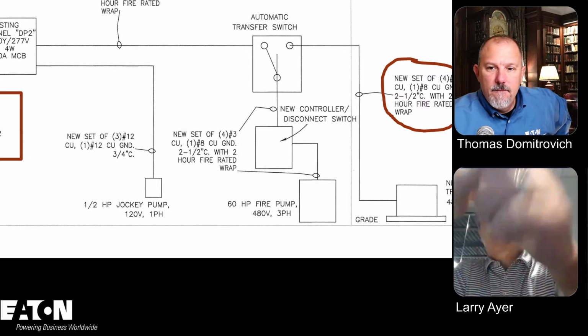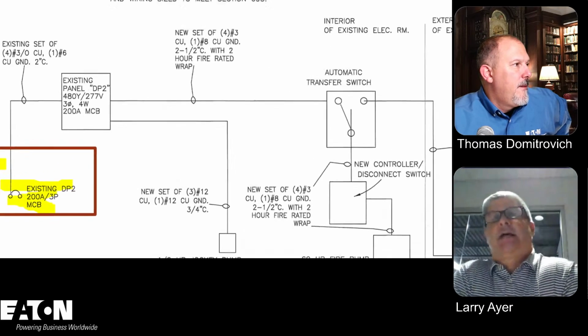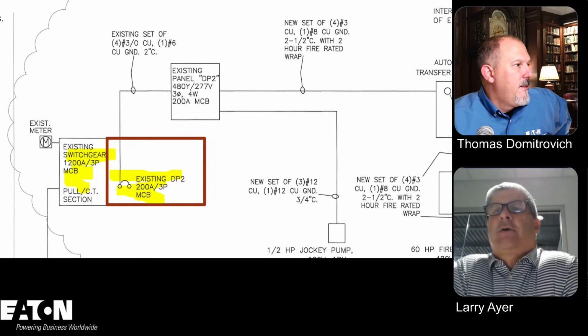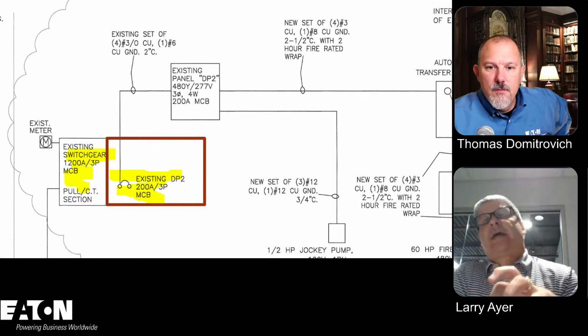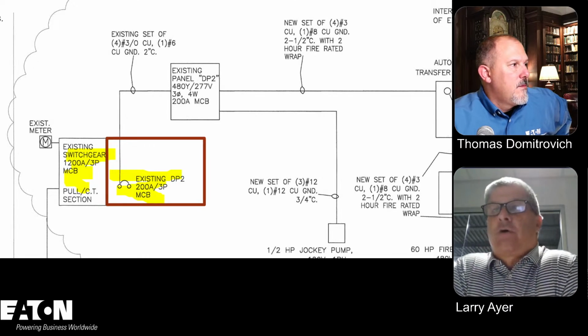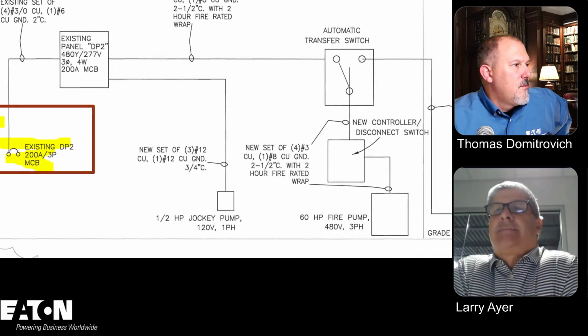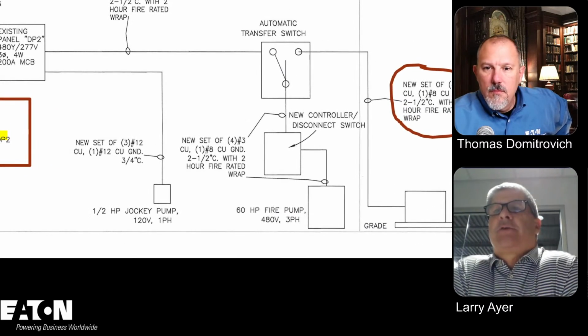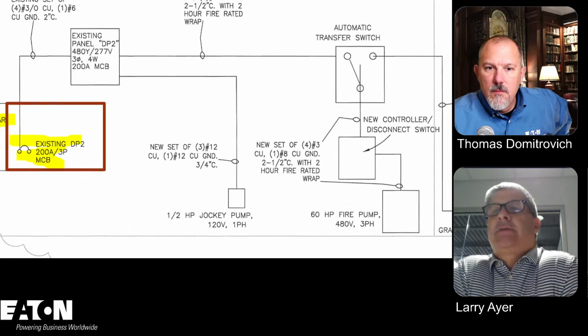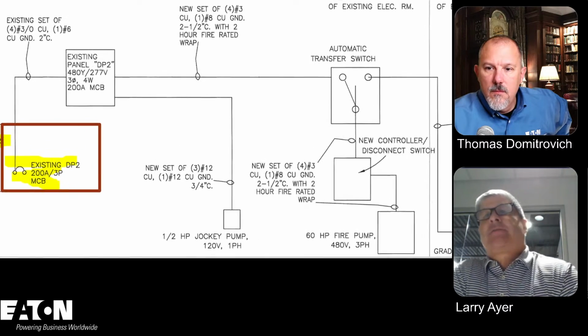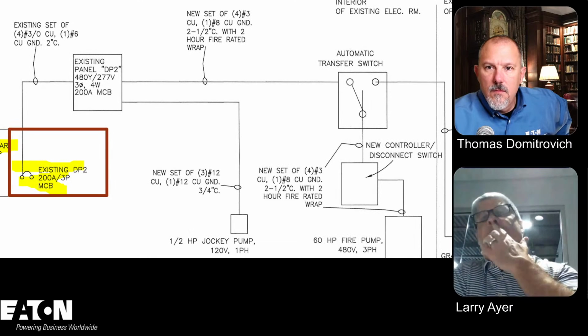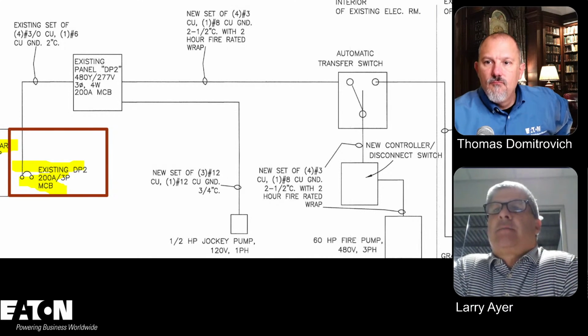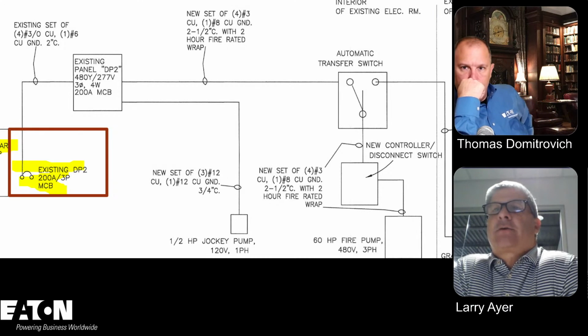So if you go back, he only has, I think, in that existing panel DP2, only a 200 amp main circuit breaker panel. So we don't have a 6 times the locked rotor. So we don't have that set up. But if you notice in there, he does have 2.5 inch conduit up there. Now that's a 60 horsepower pump, which I would assume is going to be probably around 80 amps or so.